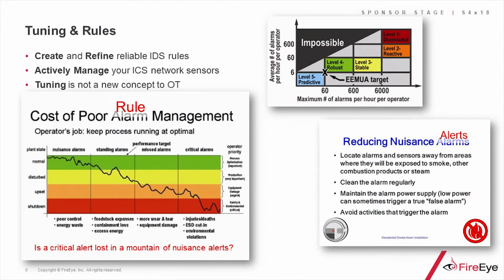We want to make sure we can ingest new rules, continuously tuning your system to detect these things. It's not a new concept to operators - that's what I'm basically trying to get at. So some of these slides are from EEMUA, about how many alarms per hour is acceptable for an operator, and reducing the number of nuisance alarms.